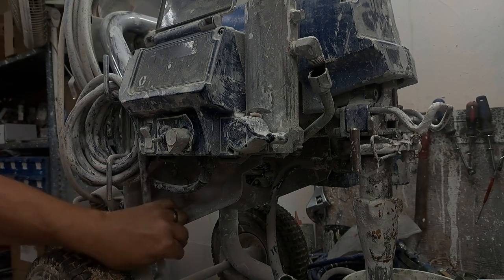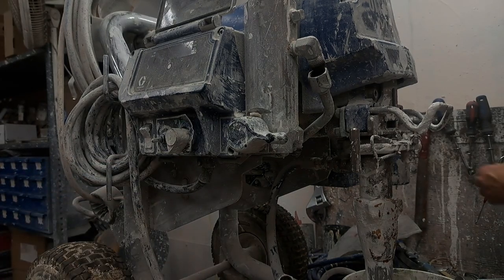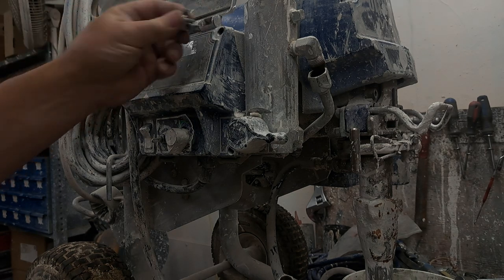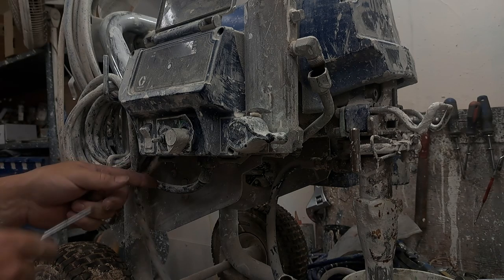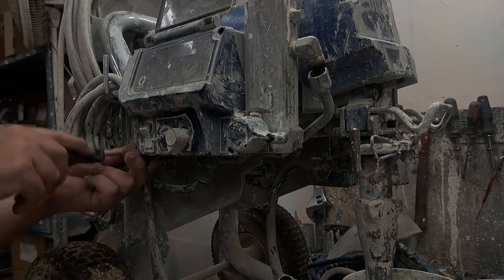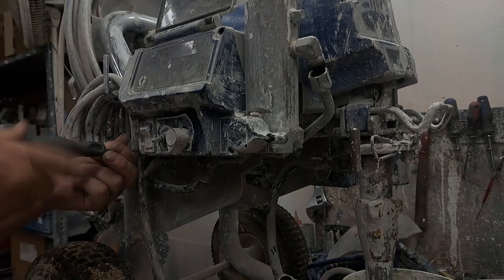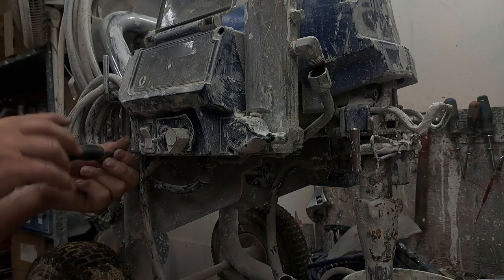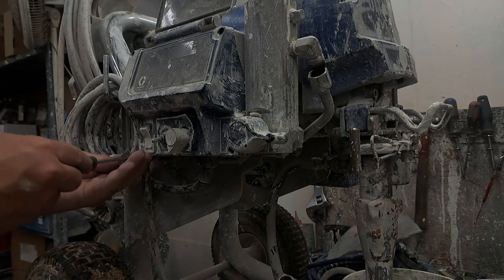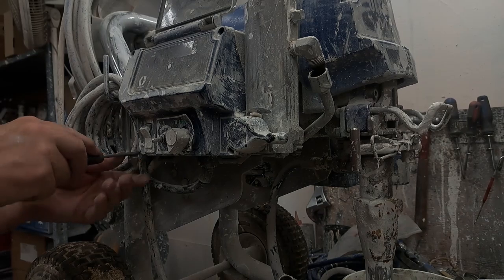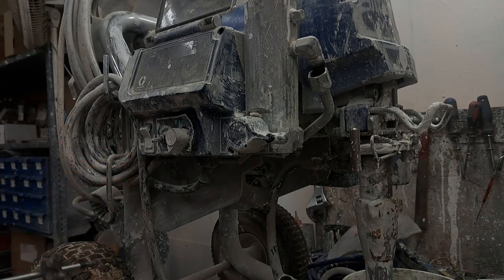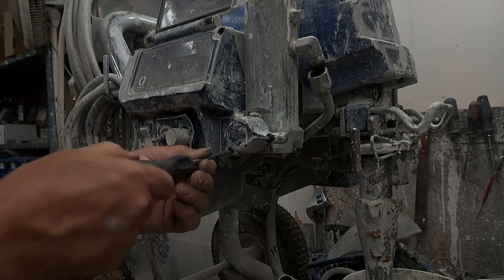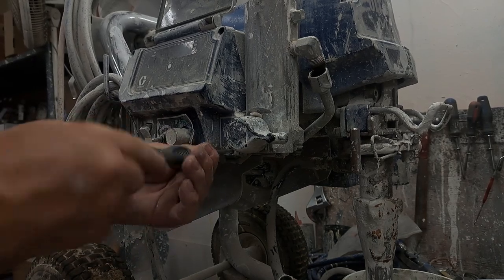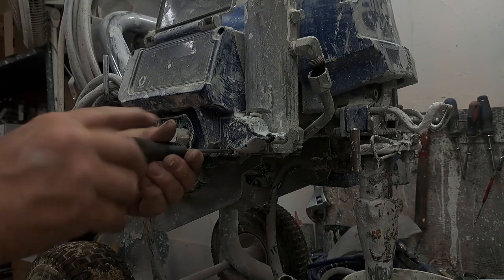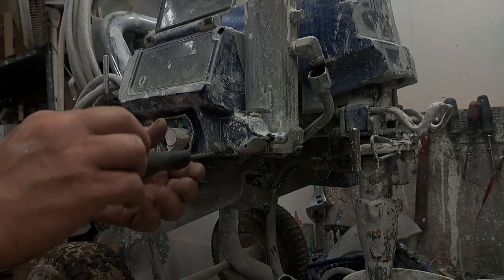But like I said, still going back to the same thing. The transducer measures the pressure. When it reaches whatever pressure you have asked for, it turns it off. When they go bad, they can either give a signal that it's at the pressure that you want, which is what this is doing, or it can show low pressure. So no matter what you set it on, it's going to say your pressure is too low, and it's going to cause the motor to keep running, and when it does, it'll over pressurize. And at that point, you can rupture a hose, damage packings, blow out a prime valve, all kinds of good stuff. That happens a lot as well.